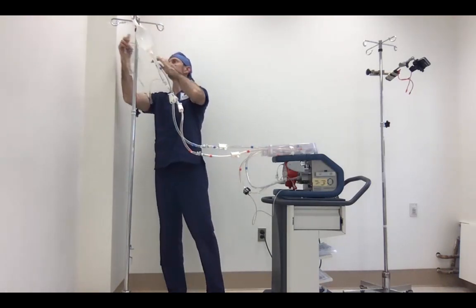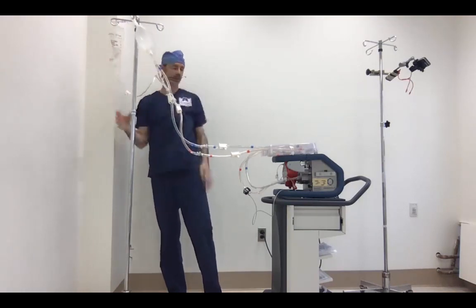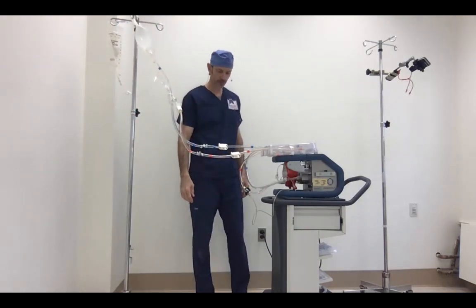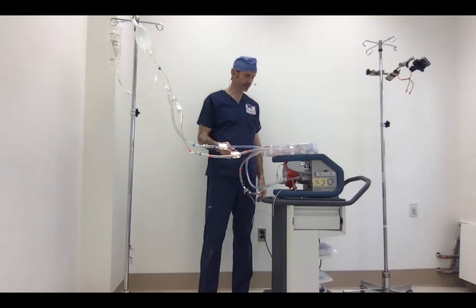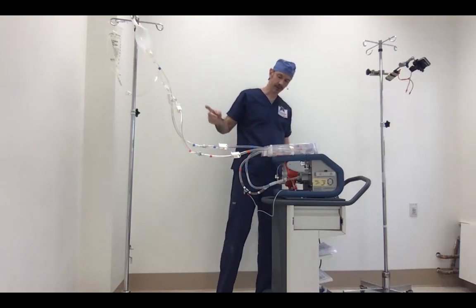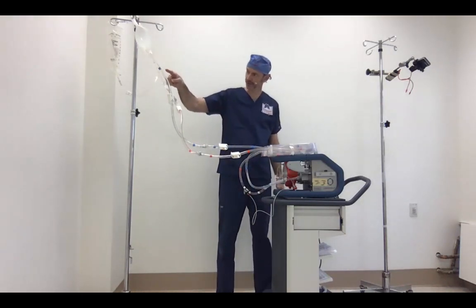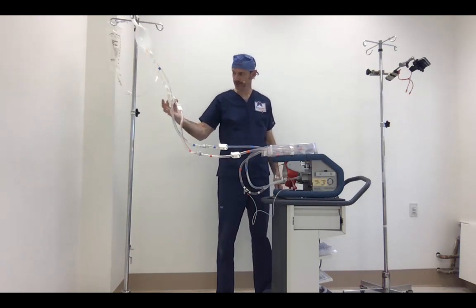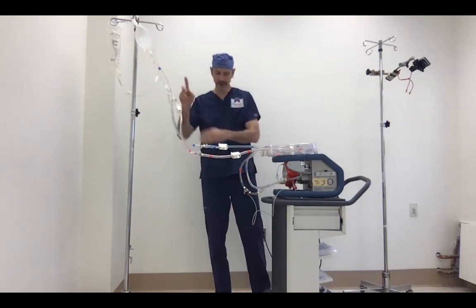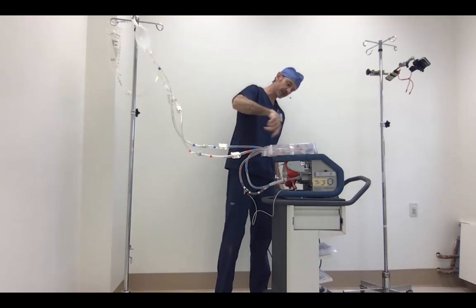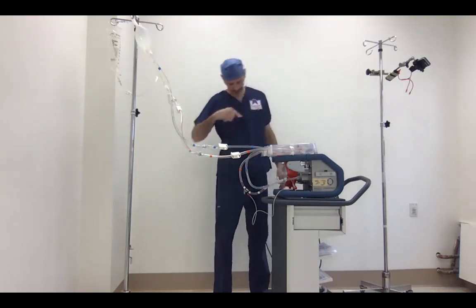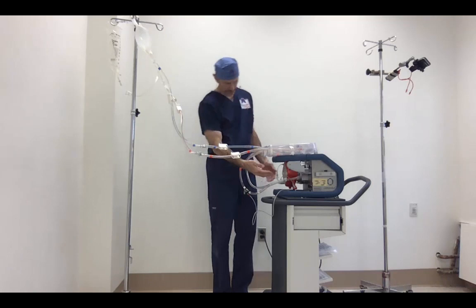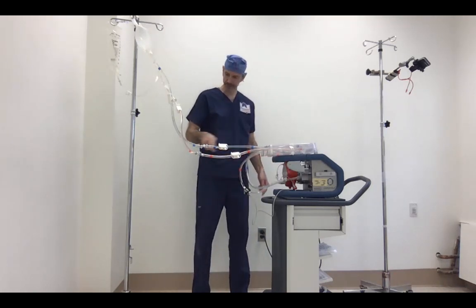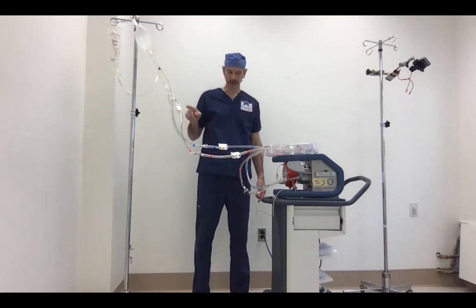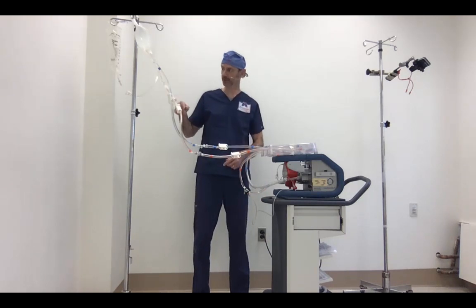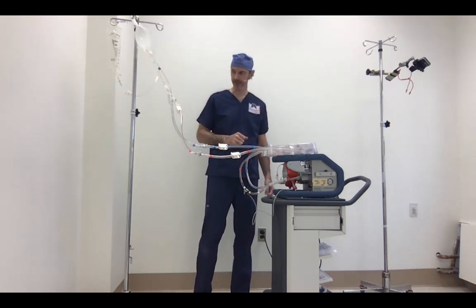Now we have our prescribed 30 inches of height. Go ahead and open the clamps. And the gravity is going to run down the venous line. It can't come down the arterial because of this fish mouth valve. And going down the venous line, zip through the loop here, go down into the oxygenator, fill the oxygenator, back up the arterial side, and there'll just be some air left in the arterial that we will push through once that pump is primed.